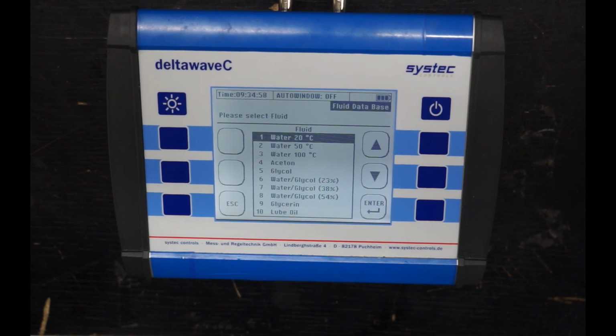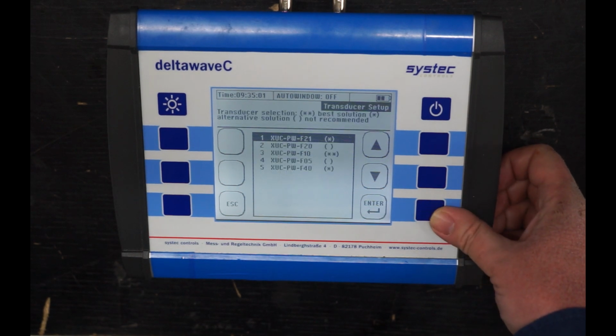The next parameter to be entered is the type of fluid flowing through your pipe. deltawaveC has a list of different fluids. If the fluid you are trying to measure is not part of the preset list, you can define up to 4 own fluids and save them on your portable device. In our case, the medium we are measuring is water at room temperature, so around 20 degrees Celsius, which is about 68 degrees Fahrenheit.